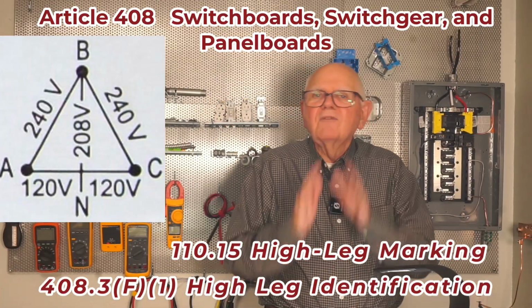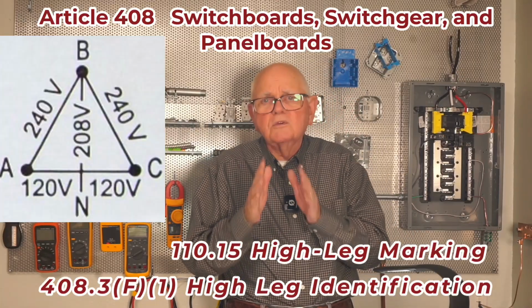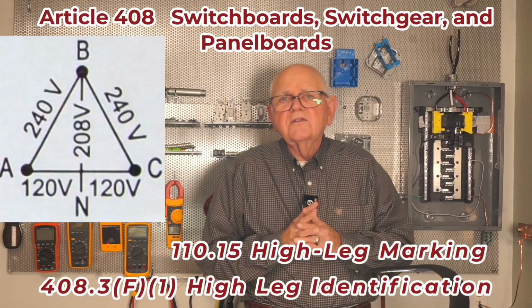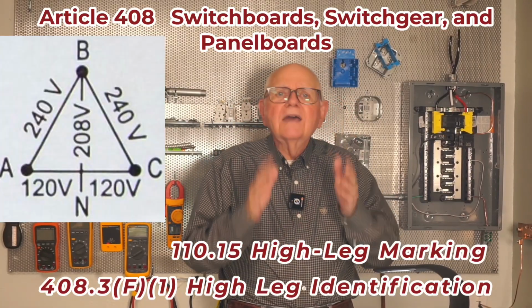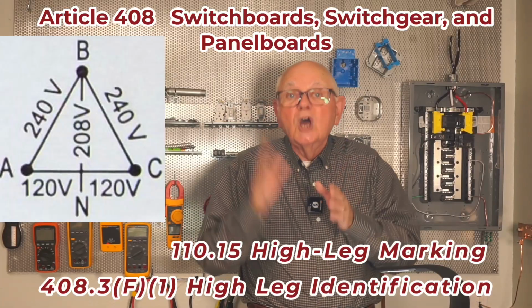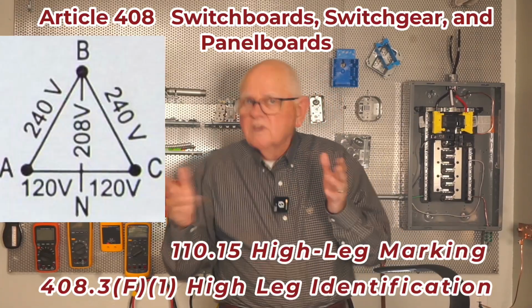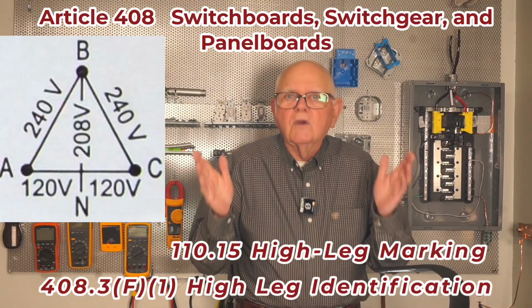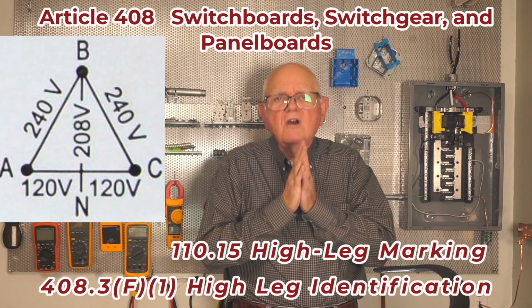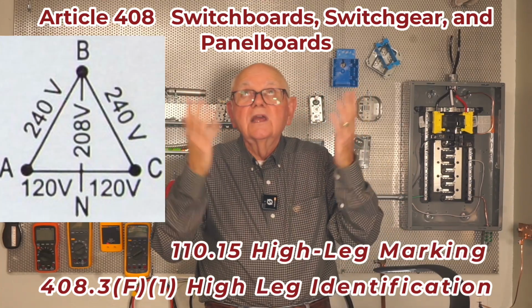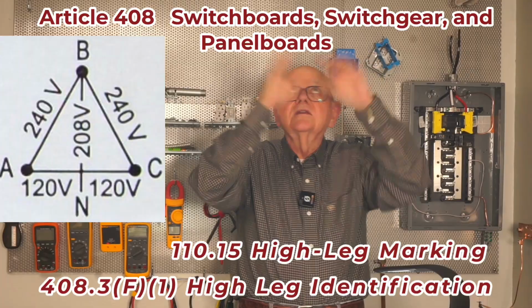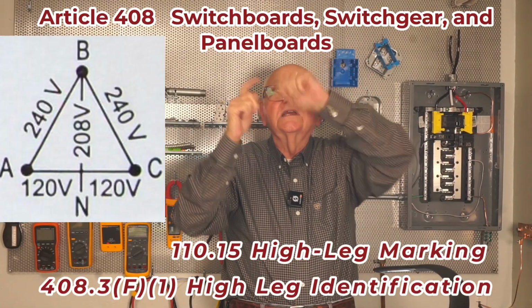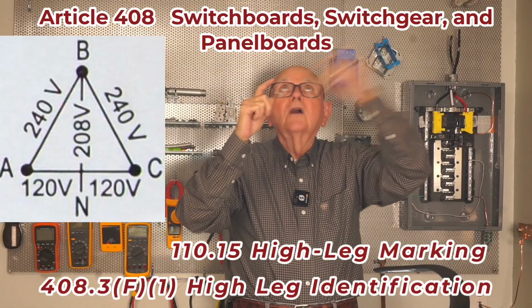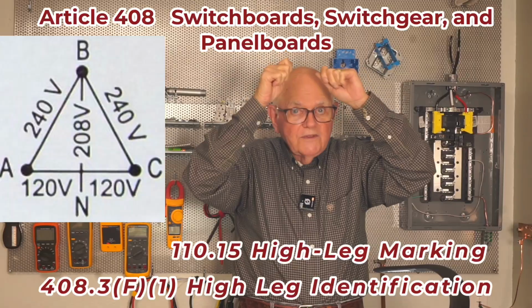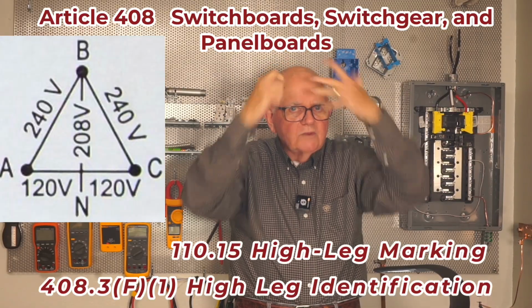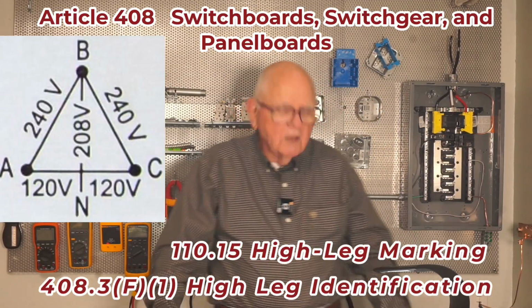So 110.15 says if I have a high leg like that, the leg up on the top, I have to identify that high leg by either orange or some other effective means, which I've always seen as orange anyway. So we make that conductor orange. That way when I go into that J box and reach up there, looking for a neutral, that's the white wire, that's easy. And I need a phase conductor. Oh, be careful, don't grab the orange one, because if I grab the orange one, I've got 208 volts going to my 120 volt load.